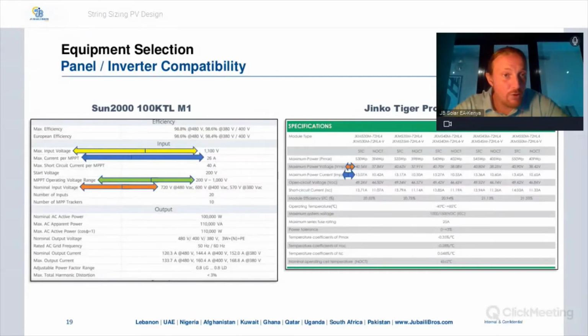And then the blue arrow on the left is the max current per MPPT. It's 26 amperes. And on the right, the blue arrow is the maximum power current. So that means this is the current that your panels will generate at peak sunlight. So if you can see closely there, it's 13 amperes on the panels. That is the maximum power current. And on the left side, max current per MPPT is 26 amperes.